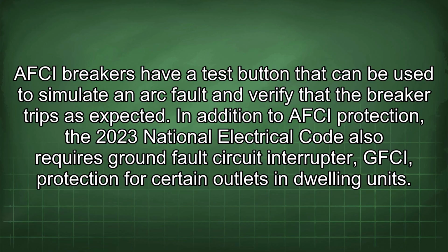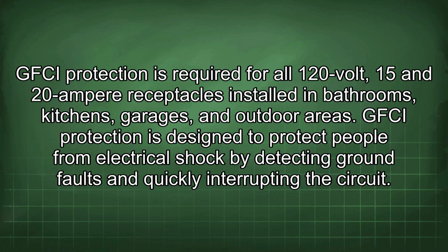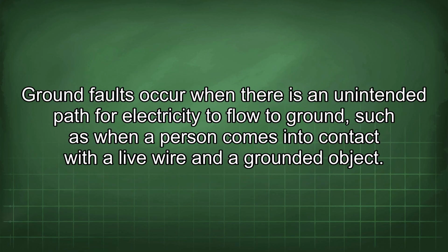protection for certain outlets in dwelling units. GFCI protection is required for all 120 volt, 15 and 20 ampere receptacles installed in bathrooms, kitchens, garages, and outdoor areas. GFCI protection is designed to protect people from electrical shock by detecting ground faults and quickly interrupting the circuit. Ground faults occur when there is an unintended path for electricity to flow to ground, such as when a person comes into contact with a live wire and a grounded object.